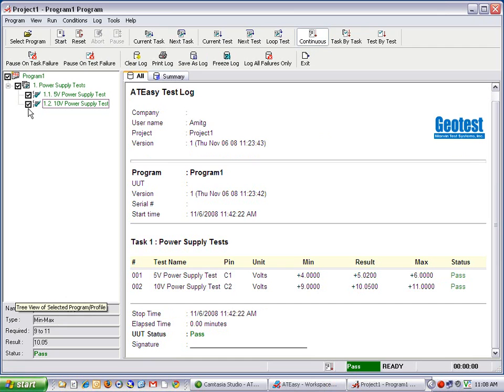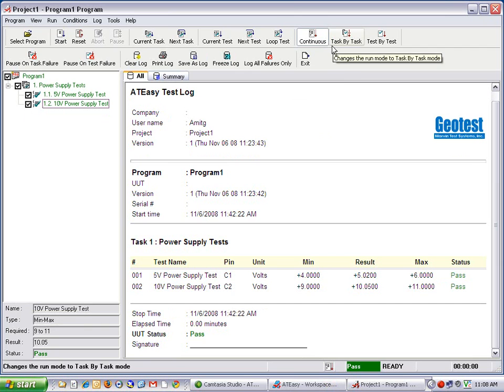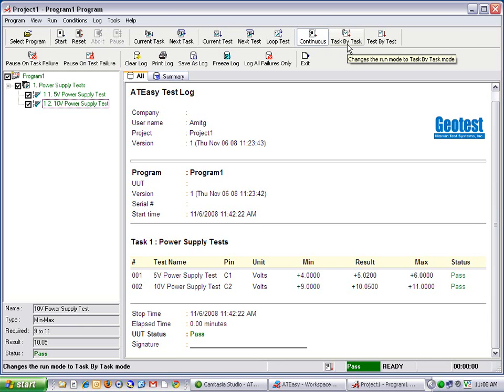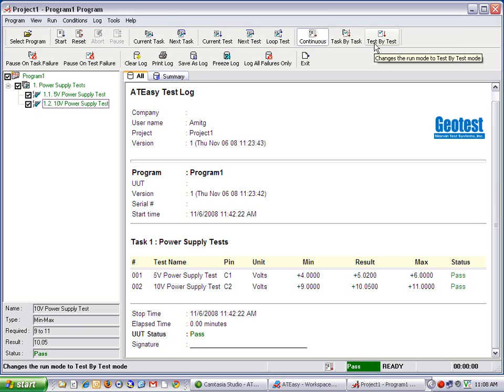The ATEasy test executive also provides several options for the test station operator, such as program flow and graphical representation. As far as program flow is concerned, the test operator has several modes to choose from, including continuous mode, where the tests are run continuously from the beginning of the test program to the end, task by task, where each task is run and then paused, and test by test, where each test is run and paused.